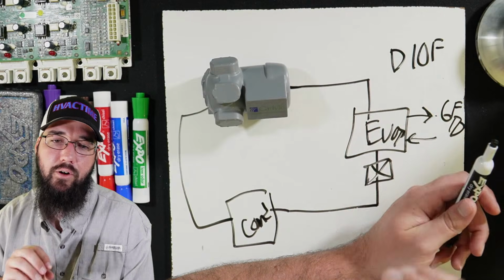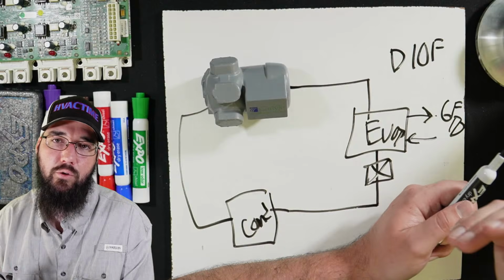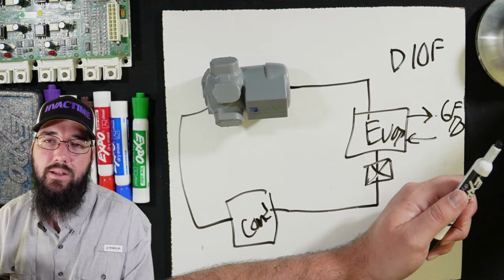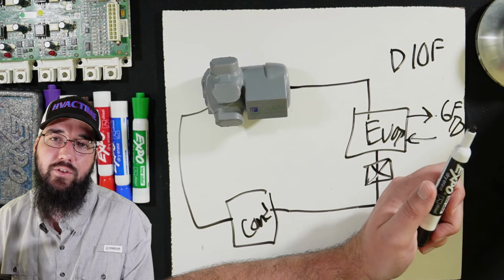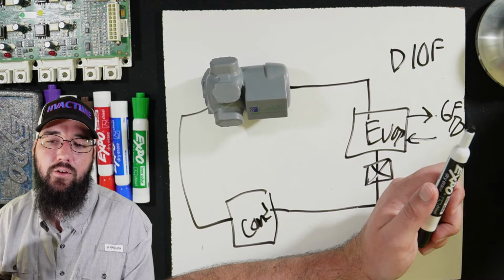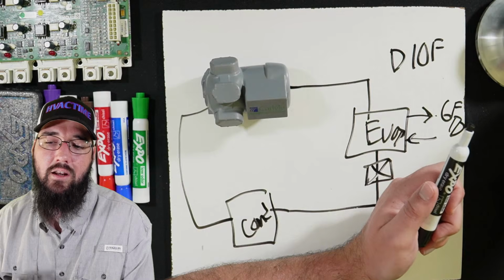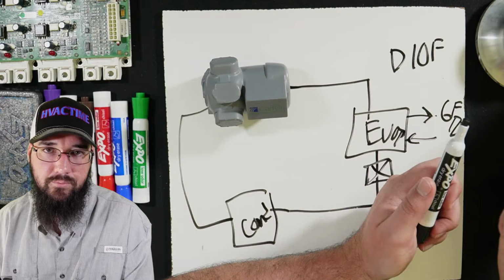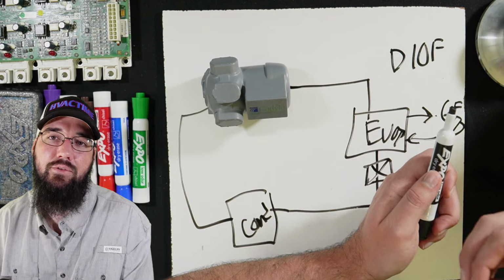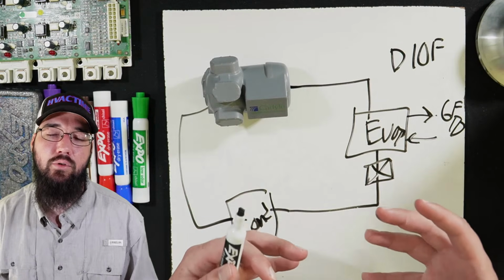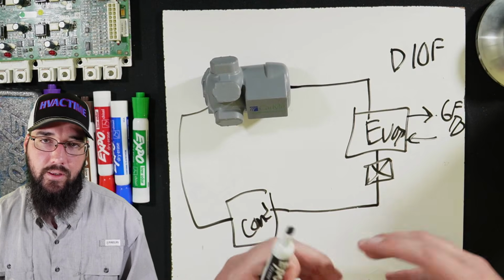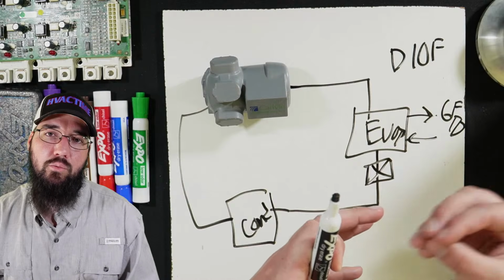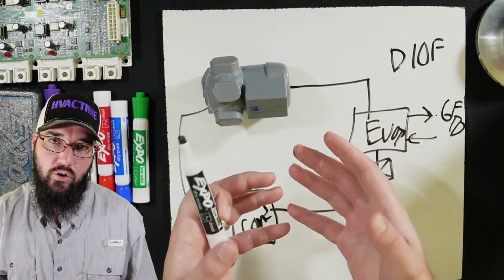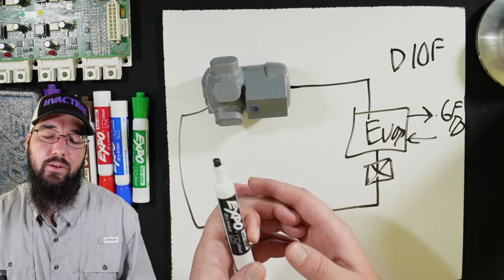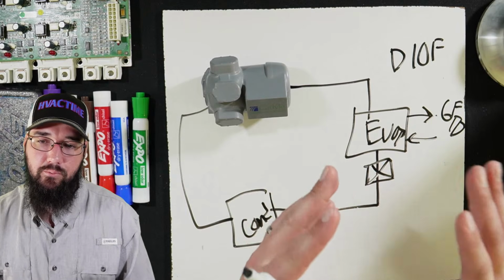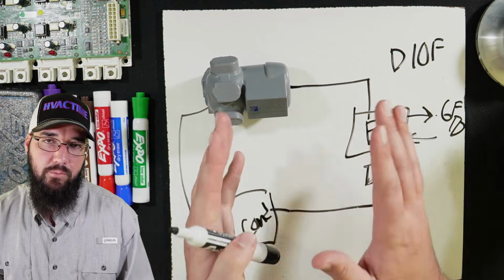Something like fouling, where we're not exchanging heat correctly, increases approach because to move the BTUs, we have to have a higher temperature difference, because there's an insulator: the fouled tubes, the mud or whatever it's gotten in there, the scaling on the tubes is not allowing heat transfer correctly. That's an insulation, which means to overcome that insulation, we have to run a higher approach. The system will naturally run a higher approach in order to overcome that insulator, so that we can still move the correct BTUs to fulfill our goal, which is leaving water set point. Again, I'm really trying to be careful with how technical I get with this. So if I'm losing anybody, I apologize.